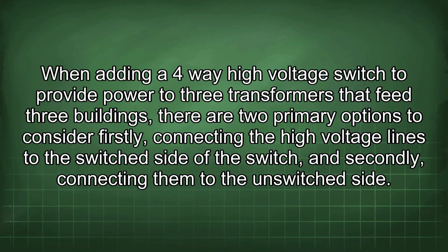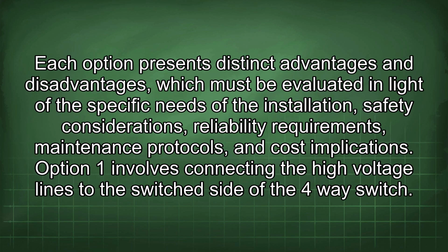When adding a 4-way high-voltage switch to provide power to 3 transformers that feed 3 buildings, there are 2 primary options to consider. Firstly, connecting the high-voltage lines to the switched side of the switch, and secondly, connecting them to the unswitched side. Each option presents distinct advantages and disadvantages, which must be evaluated in light of the specific needs of the installation, safety considerations, reliability requirements, maintenance protocols, and cost implications.